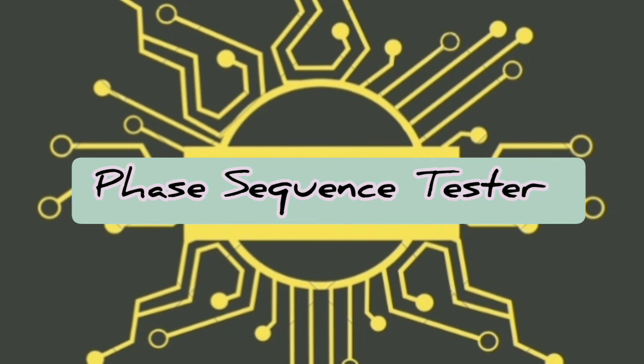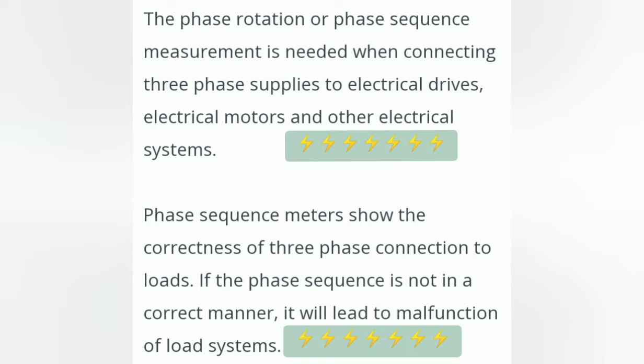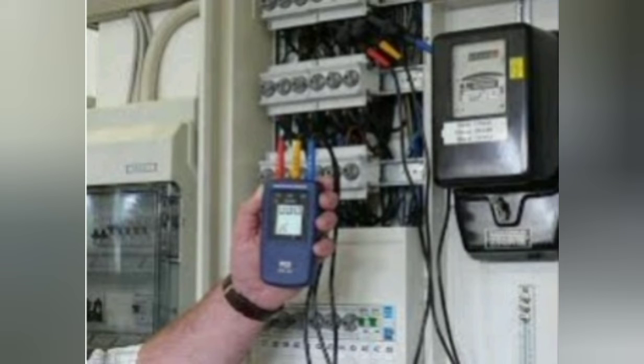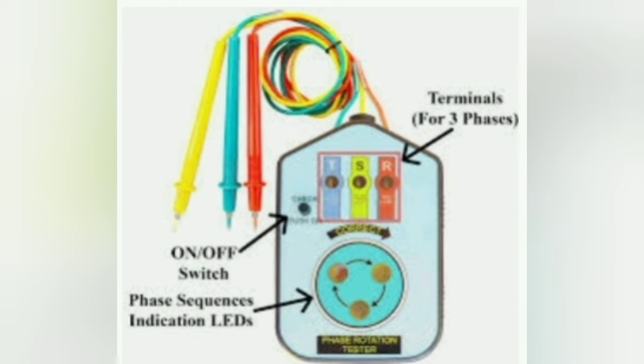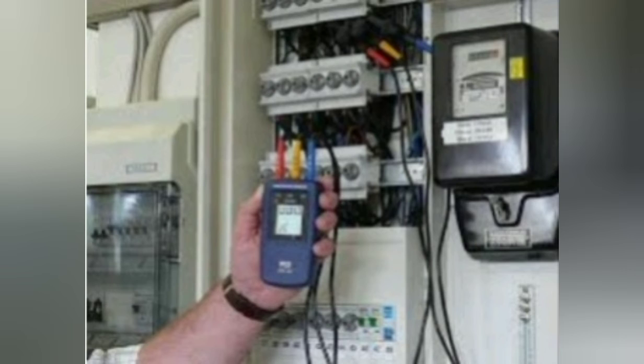Another measuring instrument is the phase sequence tester. The phase rotation or phase sequence measurement is needed when connecting three-phase supplies to electrical drives, electrical motors, and other electrical systems. Phase sequence meters show the correctness of three-phase connection to loads. If the phase sequence is not correct, it will lead to malfunction of load systems. Phase sequence testers are useful portable devices designed to check the direction of phase rotation in motorized machinery with three-phase supplies. These testers provide LED indication of both clockwise and counterclockwise rotation. Correct phase sequence is needed to avoid malfunctioning of equipment and serious damage to the load.